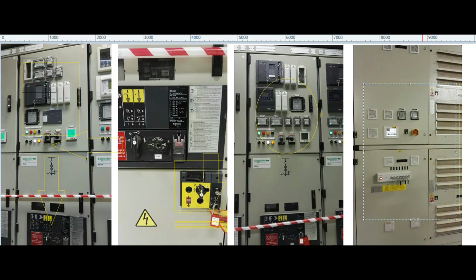And finally, this is the 6.6 kV VFD cubicle. This is the variable frequency drive. So power supply is coming from the upstream 6.6 kV switch gear, 6.6 kV panel to this VFD panel, and from this VFD to the motors located at field. So this is 6.6 kV variable frequency drive. This is also installed standalone floor mounted. This is particularly for this boiler feed pump high rating motors. So this VFD is also floor mounted and standalone panel. This is 6.6 kV.